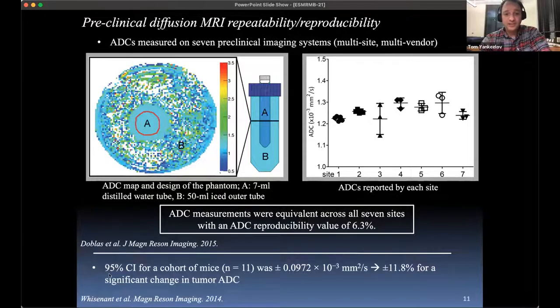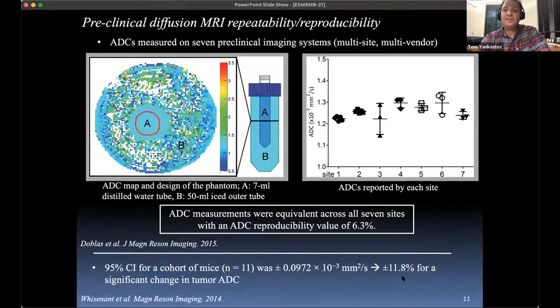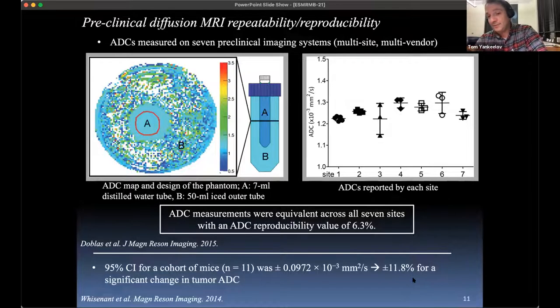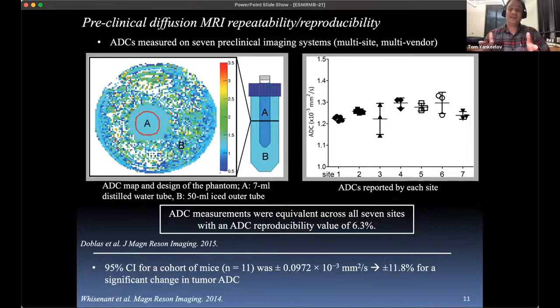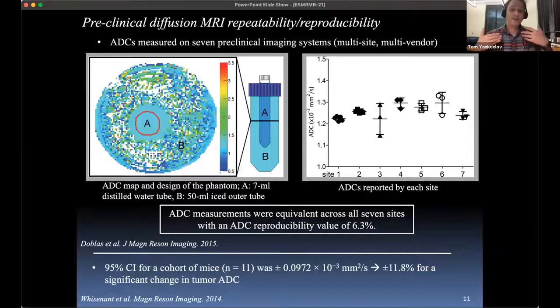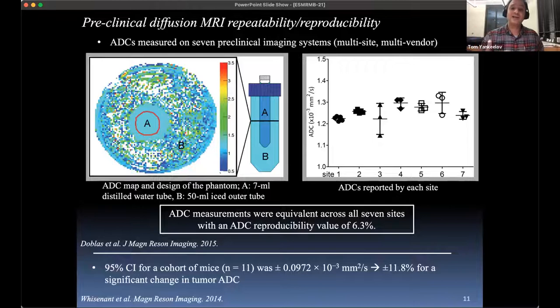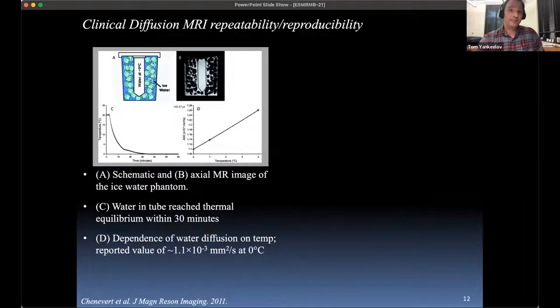Around the same time, we did a study for a cohort of mice and found that the 95% confidence interval for the ADC measurement had about a 12% change threshold — meaning you'd have to see at least a 12% change to say that change was due to biology rather than measurement error. These were studies where you put the mice in, do the diffusion measurements, take them out, wait about two hours, put them back in, do registration to get approximately the same section of tissue, and make the same measurement. The error is about 12% on one scanner at one place.